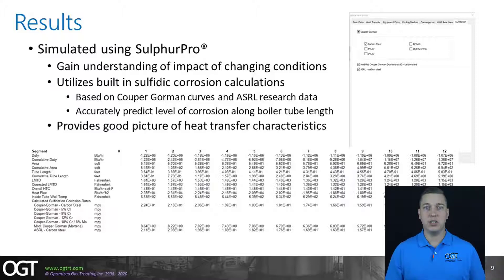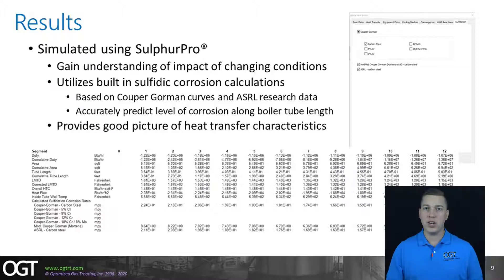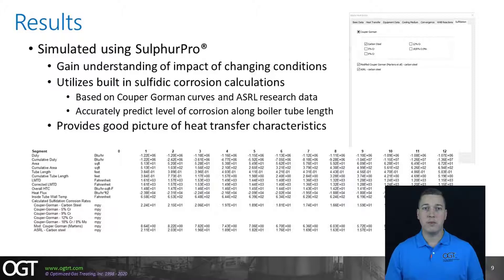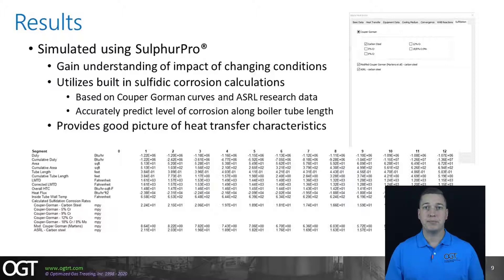SulphurPro also gives detailed descriptions of the heat transfer occurring along the length of the boiler tubes, calculating heat flux, tube wall temperature, and mass flux, among others. A screenshot shows both the input on the right side and the output on the bottom. You can see a choice of which corrosion model to use as well as what metal types to look at for the original Couper Gorman curves. On the output screenshot, the waste heat boiler is segmented along the length of the boiler tubes, providing a ton of information: duty, LMTD, overall heat transfer coefficient, heat flux, inside tube wall temperature, and the sulfidation corrosion rates at each segment — a truly detailed image of what is happening inside that equipment.